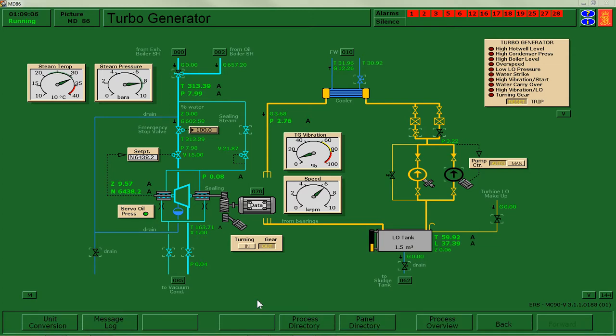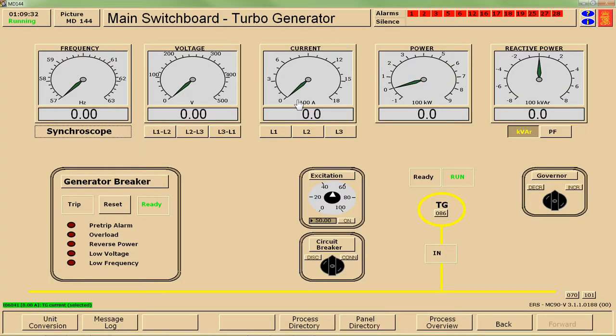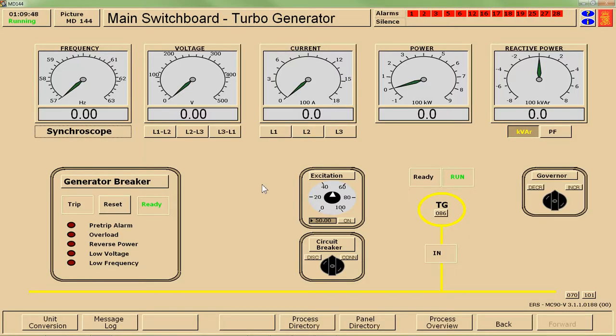I'm going to use my steam turbine — I've just got it up and running — and we're going to take a look at how we would go about synchronizing it. We're going to go to my panel directory and go to page 144, which is my main switchboard for my turbo generator. If you were using a different generator, you would go to its main switchboard page.